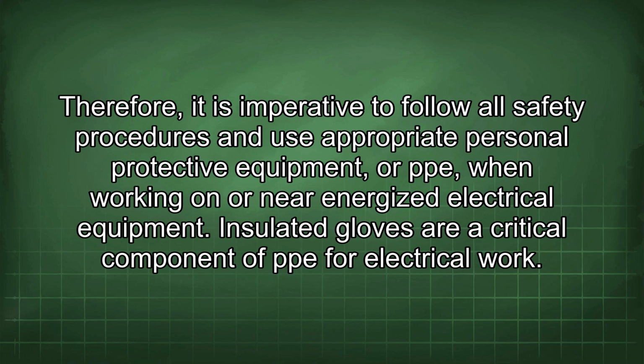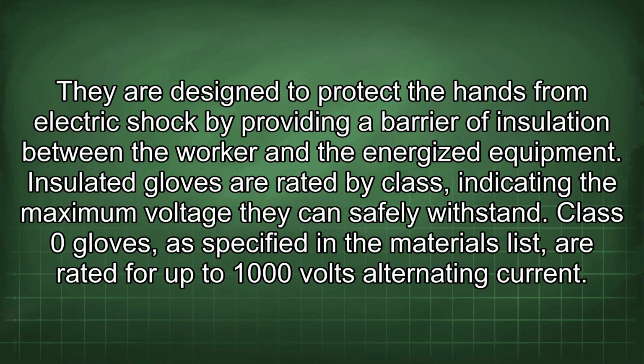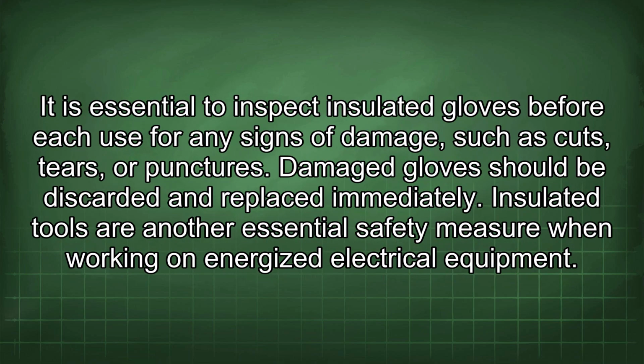Insulated gloves are a critical component of PPE for electrical work. They are designed to protect the hands from electric shock by providing a barrier of insulation between the worker and the energized equipment. Insulated gloves are rated by class, indicating the maximum voltage they can safely withstand. Class 0 gloves, as specified in the materials list, are rated for up to 1000 volts alternating current. It is essential to inspect insulated gloves before each use for any signs of damage, such as cuts, tears, or punctures. Damaged gloves should be discarded and replaced immediately.